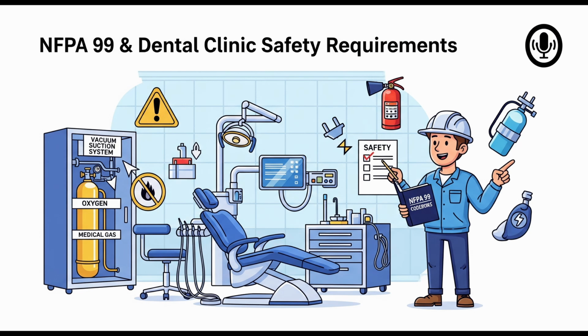So where can you keep them? Well, the location matters. If it's an indoor storage room or enclosure, the construction materials inside need to be non-combustible or limited combustible. You need enough space to safely move cylinders in and out, usually with a hand truck, and the area must be secured, locked, or otherwise protected from unauthorized people getting in. Makes sense. Temperature is also a factor. You have to protect cylinders, full or empty, from getting hotter than 52 degrees C, which is 125 degrees Fahrenheit. So no storing them right next to a furnace or in direct, intense sunlight through a window.